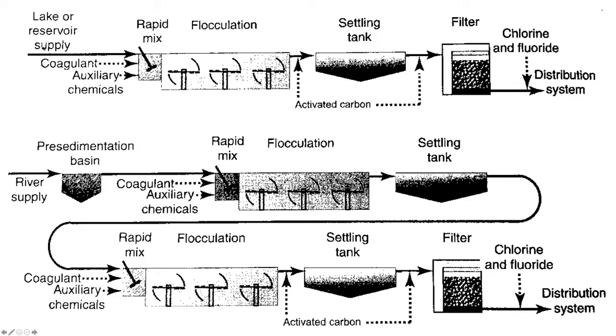For some river supplies that have higher turbidity, there might be a few extra steps in the treatment process, like a pre-sedimentation basin to remove larger materials. After that, we would go into rapid mix with coagulation, flocculation, and sedimentation. In some cases, there would be two steps of coagulation-flocculation in series, followed by sedimentation and filtration before the addition of chlorine and fluoride.